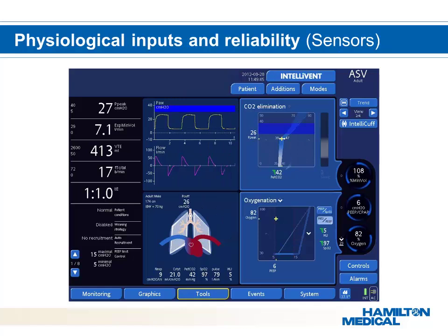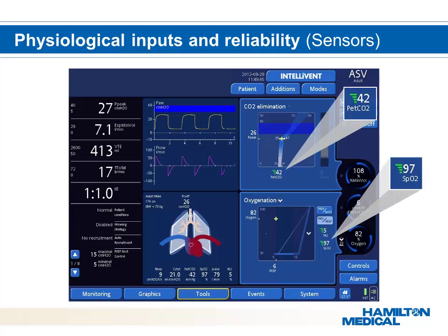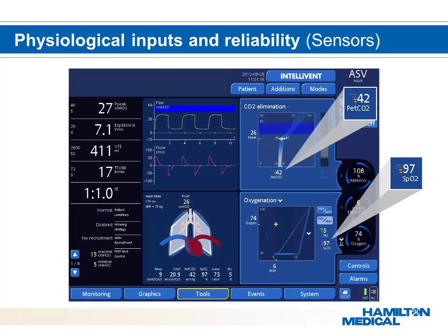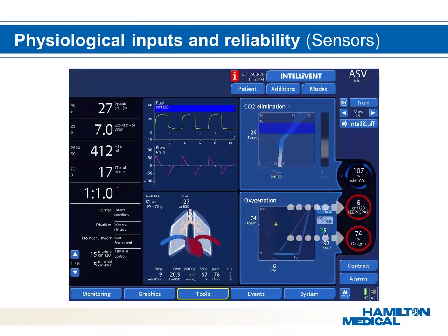IntelliVent-ASV relies on the ETCO2 and SpO2 signal. The signal can be affected by many influences, therefore quality indexes have been implemented to provide a clear overview of signal quality. If signal quality is deteriorating, the bars will change color. If the signal quality is too low, the controller will be frozen and the most recent settings will be used. In this situation, the ventilator will also alarm visually and audibly.